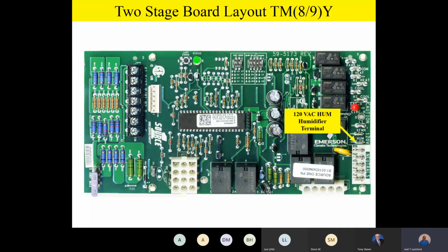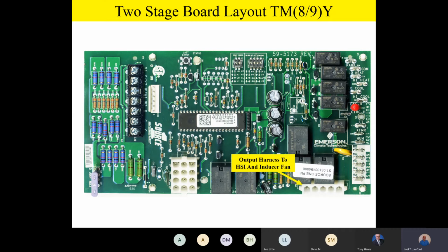Below those 120 volt outputs, we have a neutral bus. Looks like we have about 5 or 6. We have 5 terminals on that neutral bus. This is where your white wires are going to come in, and it's just a common neutral bus. Now, because this is 2-stage heat, you'll notice that we have a harness down below, that output harness to the hot surface igniter and the inducer fan, and we have additional terminals on there because it's a 2-stage product. So if you've noticed that from the last board we looked at, the last board only had 4 terminals on here. This one has 5. It's because we have a 2-stage inducer on its 2-stage heating product.